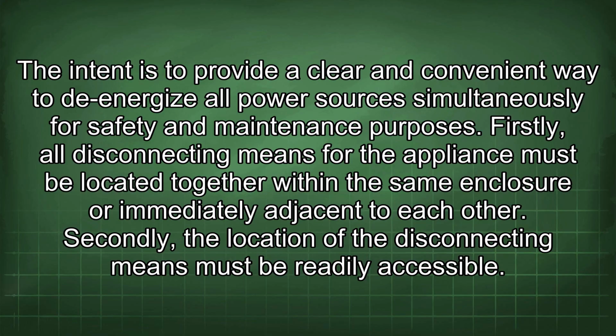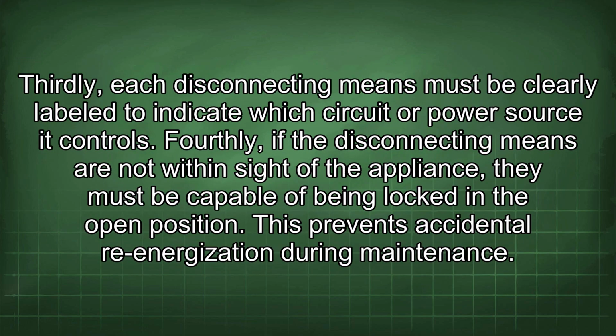Firstly, all disconnecting means for the appliance must be located together within the same enclosure or immediately adjacent to each other. Secondly, the location of the disconnecting means must be readily accessible. Thirdly, each disconnecting means must be clearly labeled to indicate which circuit or power source it controls. Fourthly, if the disconnecting means are not within sight of the appliance, they must be capable of being locked in the open position. This prevents accidental re-energization during maintenance.